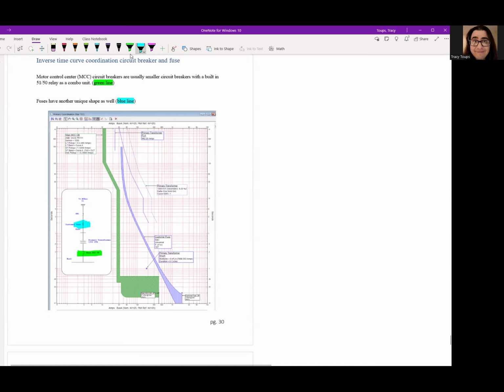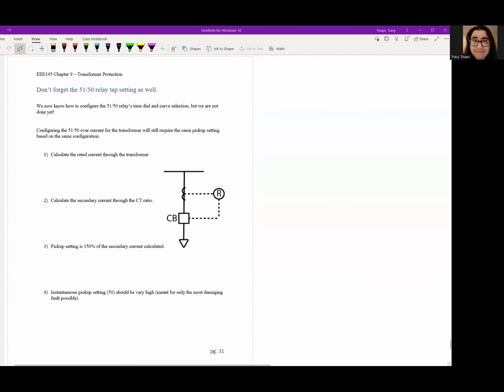All right. And then lastly, where is the transformer damage curve? You can see it's right here. Right, so here is the transformer damage curve, and that's the transformer right here being protected. Okay, so you can see the downstream devices. The fuse is with the transformer, so the fuse must be lowered to the left of the transformer damage curve. And then the motor control center is downstream of both of them, so that should be before the fuse and the transformer damage curve. You can see we're cascading them to the bottom and to the left of the page. Okay, so that's how you do your curve coordination.